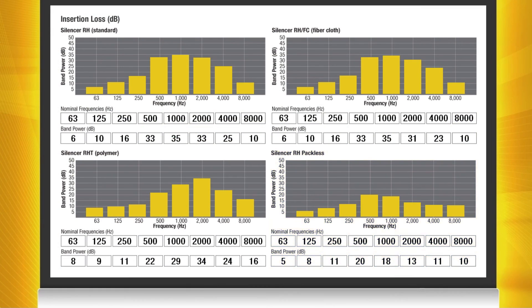You can see that the insertion loss performance through the packless silencer is less than that of a rectangular absorptive silencer. Instead of acoustic media to remove the sound energy, these silencers rely on tuned chambers to help dissipate the sound. Although they do not perform as well as an absorptive silencer, sometimes they are the best option for the application.